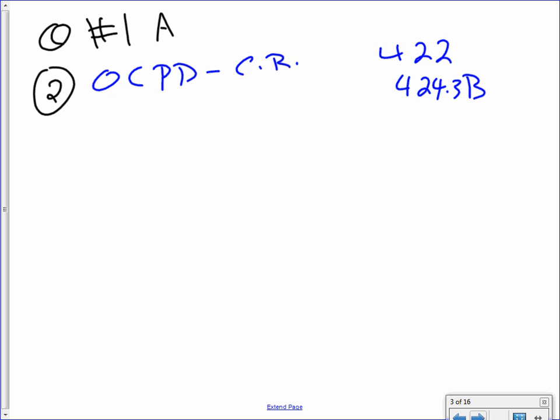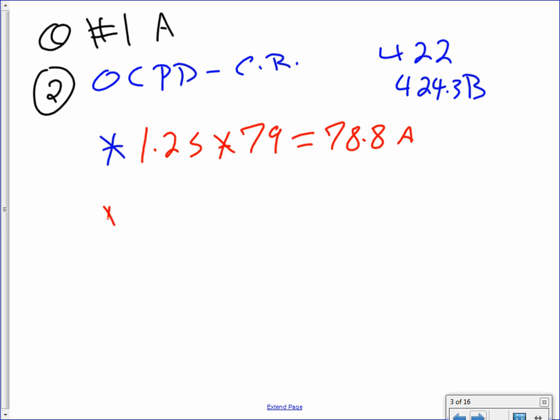424.3b for resistive heat. It will tell you the following. Take 1.25, like I told you guys, times 79. Same calculation that we've done in a second. 78.8 amps. Same calculation, no magic. Then you take the 78.8 amps. Make sure you take it to 240.6. That's where you find the standard non-adjustable circuit breakers. And that will get 80.